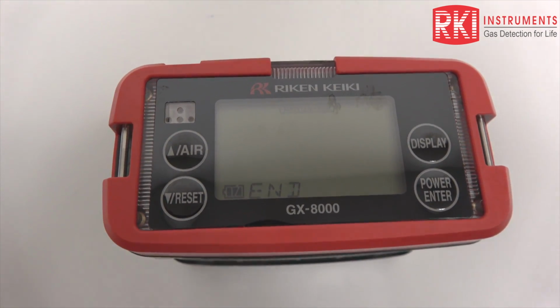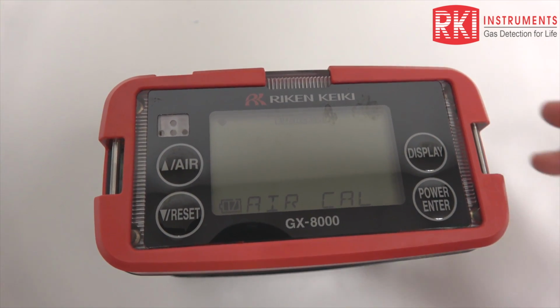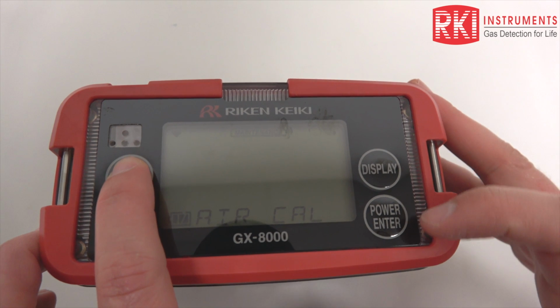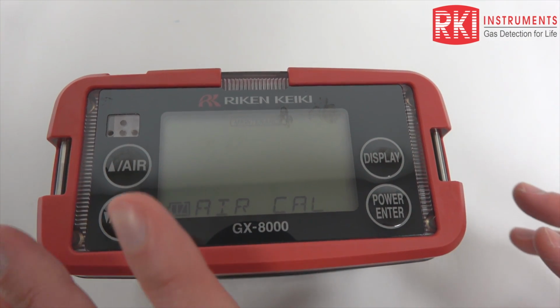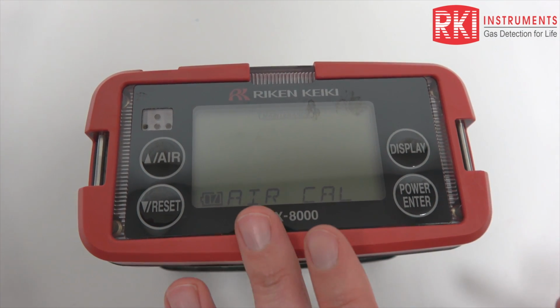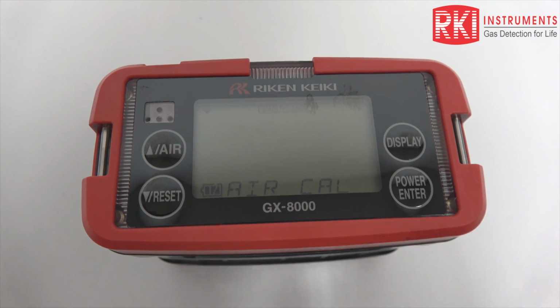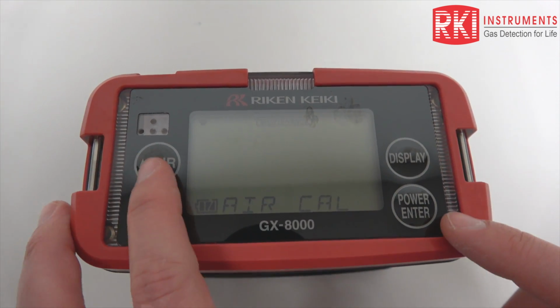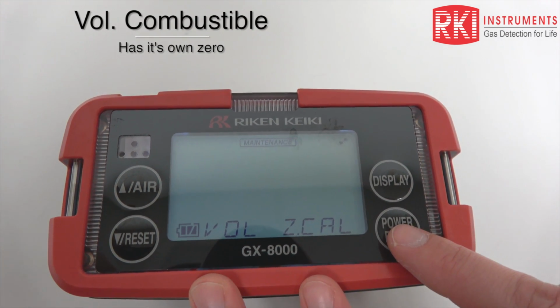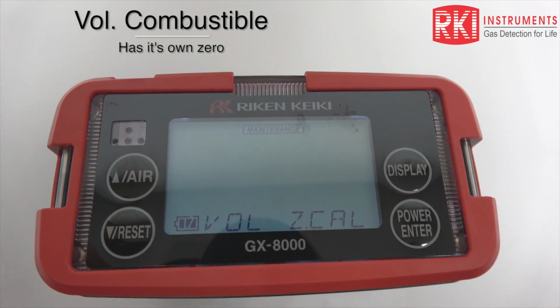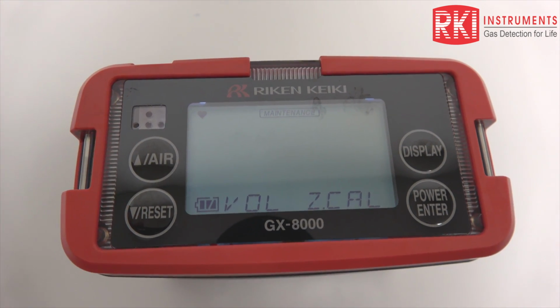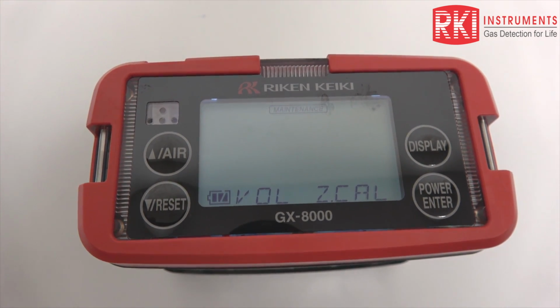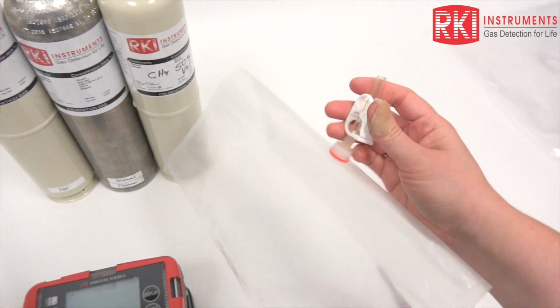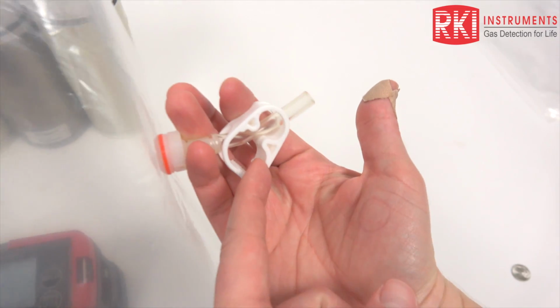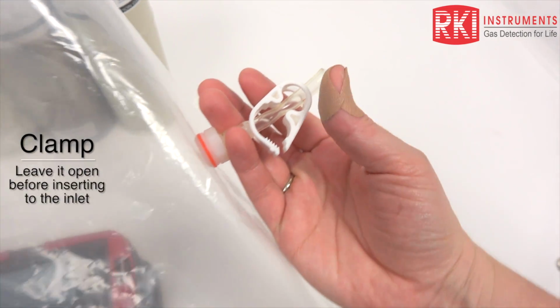So now we're done with our zero. We do need to still zero our volume sensor. So this instrument has 5 sensors: an LEL combustible, an oxygen, a CO and H2S, and then a volume combustible. And the volume combustible has its own special zero. So for this zero, we're going to use nitrogen here in this building because that's what we have. If you have inert gas, you need to use that. So I'm going to take my gas bag. This is my gas bag. It has a clamp. The clamp is open right now.